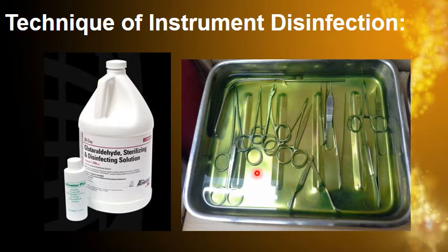They should be completely submerged under the solution. After this, I will calculate the time according to the manufacturer, for example 5 milliliter and 10 milliliter water. You should leave the instrument for half an hour, and so on. So they must be in contact with the solution for the whole designated period. I should not take them out before the designated period.